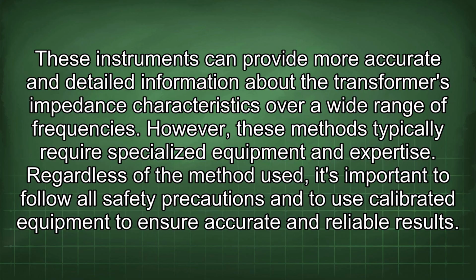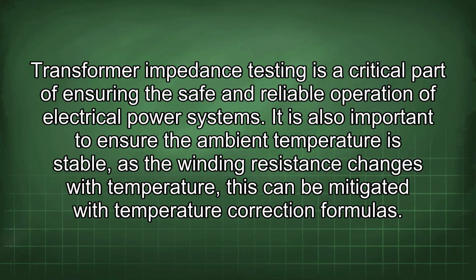However, these methods typically require specialized equipment and expertise. Regardless of the method used, it's important to follow all safety precautions and to use calibrated equipment to ensure accurate and reliable results. Transformer impedance testing is a critical part of ensuring the safe and reliable operation of electrical power systems. It is also important to ensure the ambient temperature is stable, as the winding resistance changes with temperature. This can be mitigated with temperature correction formulas.